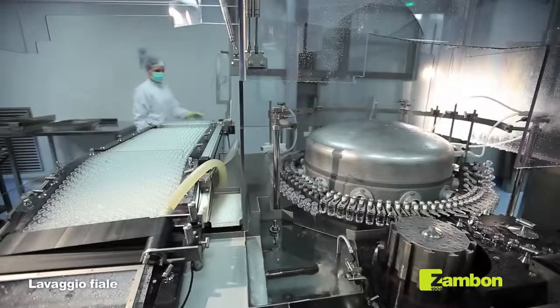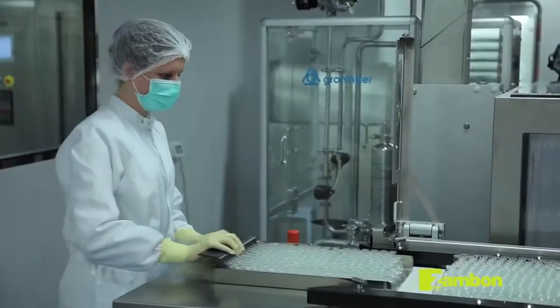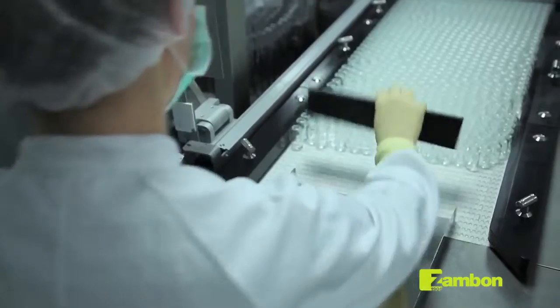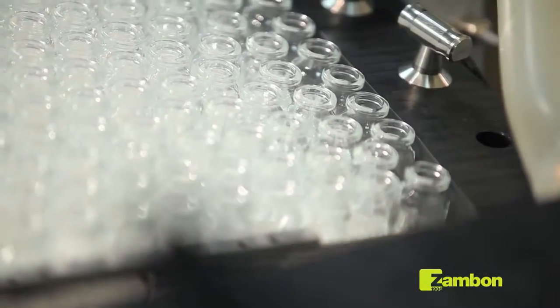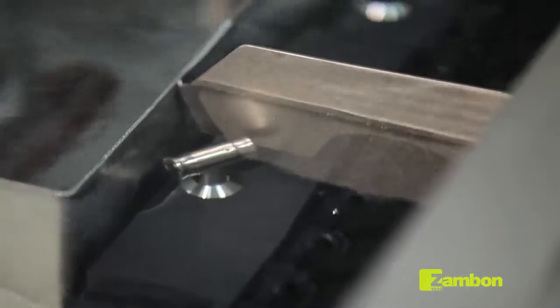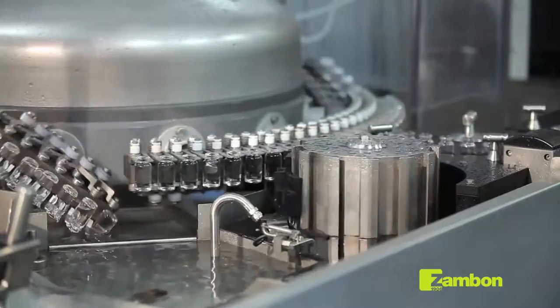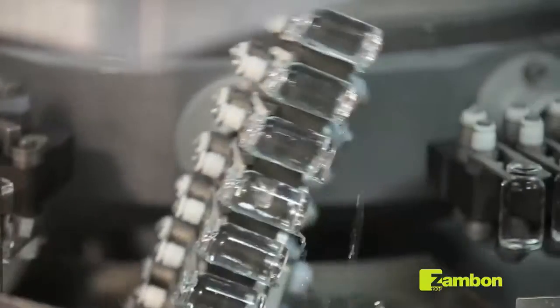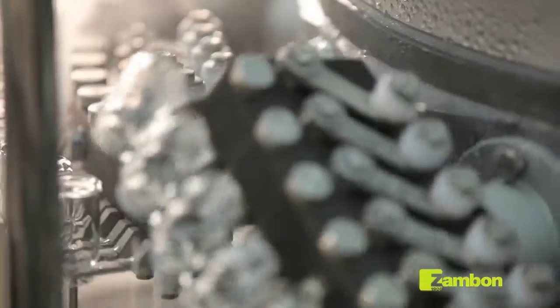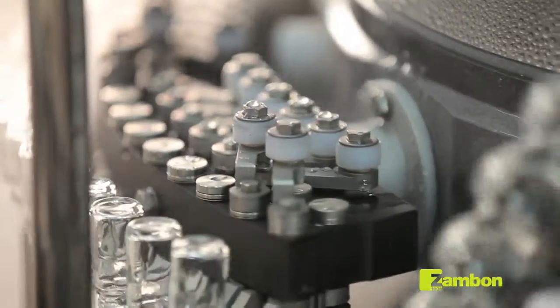The materials required for the lyophilization process are washed and sterilized in dedicated machinery. The bottles received from the warehouse are fed into the bottle washing machine by an operator, undergo a washing cycle with water for injectables at 85 degrees Celsius, and then dried with sterile filtered air. The caps and equipment necessary for the production, such as machine parts, sterile overalls, glasses, etc., undergo a sterilization cycle with pure vapor at 121 degrees Celsius in an autoclave installed in a dedicated area.